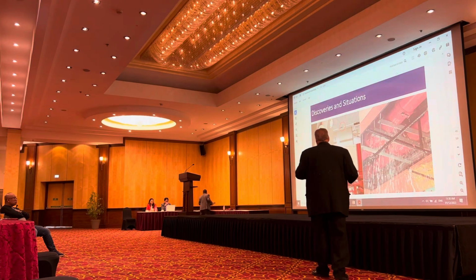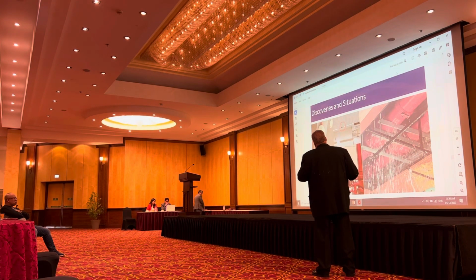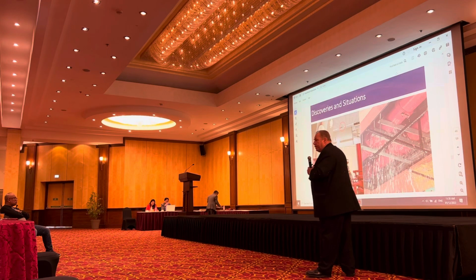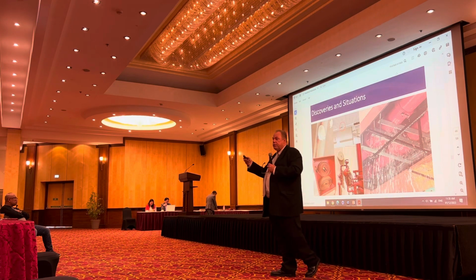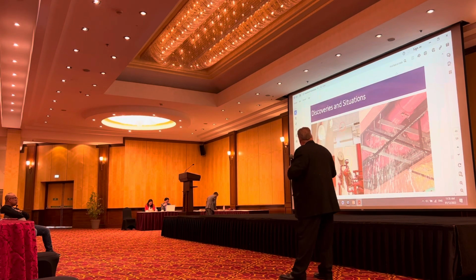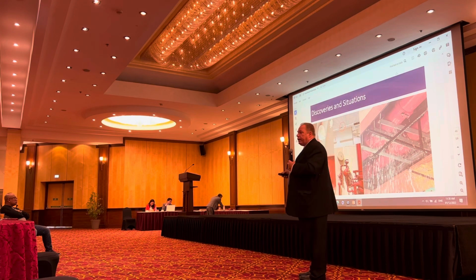Here, things happen. We found a contractor who left a glove on the smoke detector. Over here, the contractor installed the smoke detector too close to the vent - it should be about 1 meter, 3 feet, and he put it like 6 inches. So we come back and say, excuse me, I'm not paying for this. You made a mistake, change it, change it now.